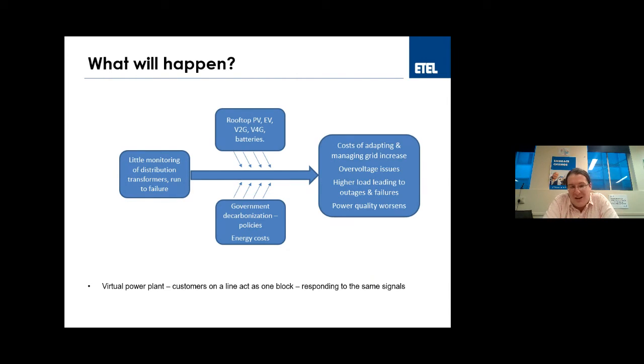On the left-hand side is the situation now, where there's little monitoring of distribution transformers and they tend to be run to failure. This has served us quite well for a while - a lot of these distribution transformers, if they stop working, it's not so much of an issue to send a truck out and replace it. But now we're starting to see other stresses coming onto it: rooftop PV, electric vehicles, and batteries at the top. We've been thinking about how these impact the reliability of the transformer.